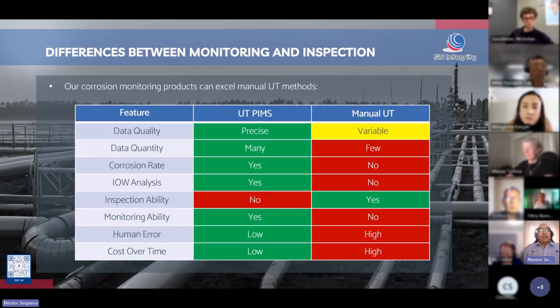Before going into details, I want to mention that in the past, we used manual UT for doing thickness tests and we call it inspection. And then when we found something and had to do it more routinely, we call it monitoring, but it was still manual UT. With the advent of new technologies, we can now have UT permanent installed monitoring sensors. If you see there, UT permanent installed monitoring sensors defeat manual UT in all of the categories except for the inspection ability because it's fixed.